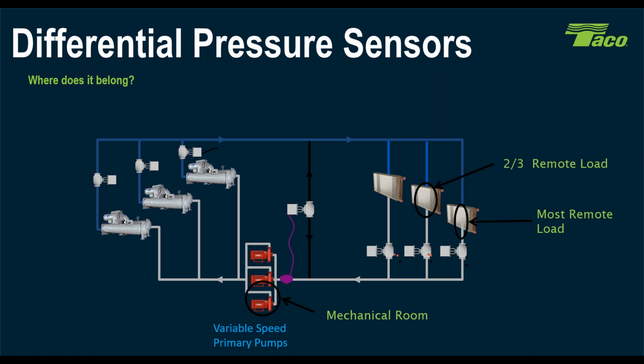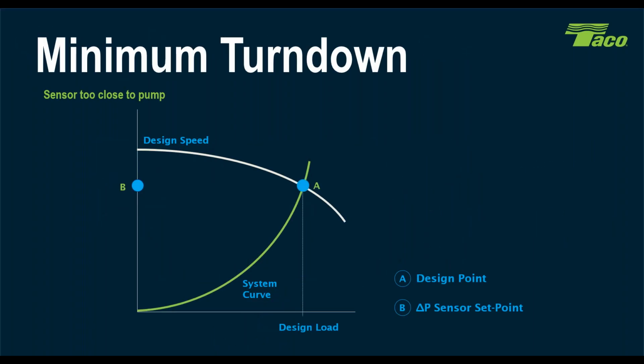And there's good and bad with all of them. It depends on where you're at in the equation. Are you the BAS contractor? Are you the mechanical engineer? Are you the building owner? The reality is all of them have their pluses and minuses. The one that you don't want to do is the mechanical room, and here's why. The closer I put the differential pressure transmitter to the pump, the less change I'm going to see.